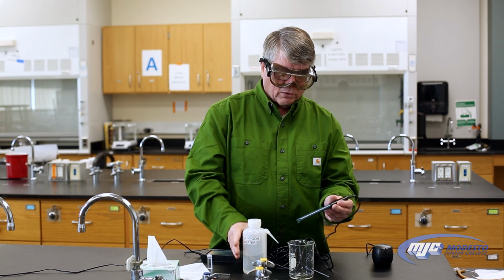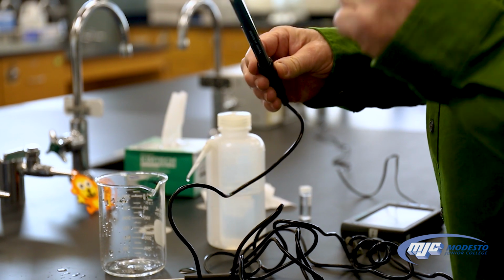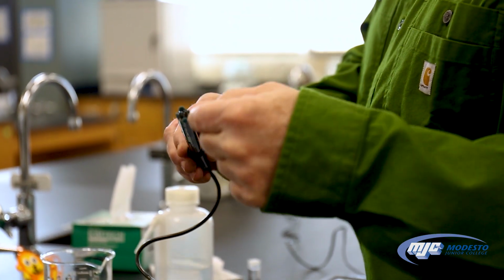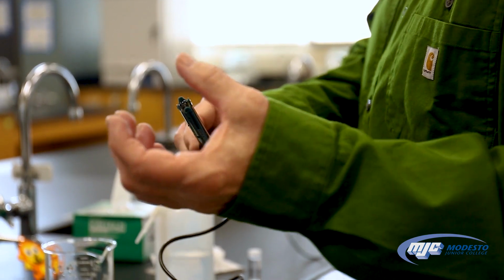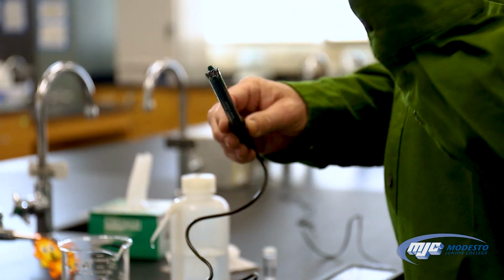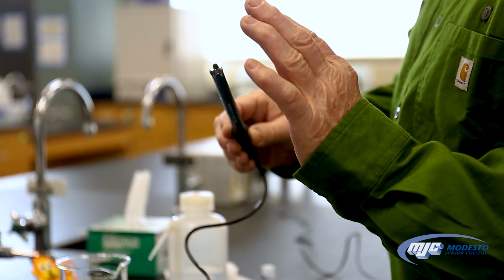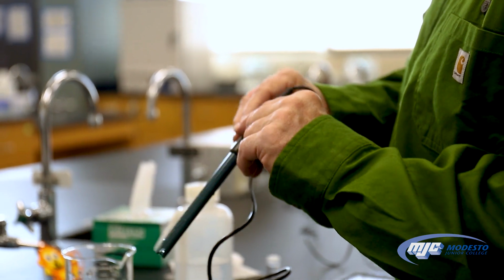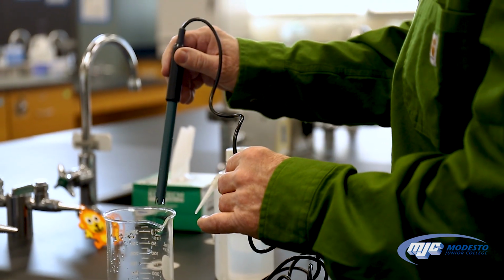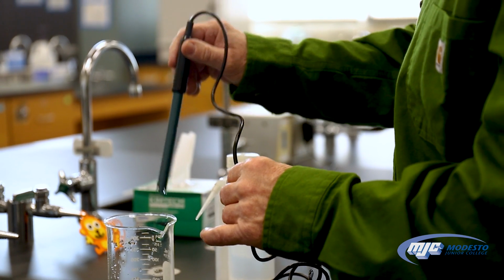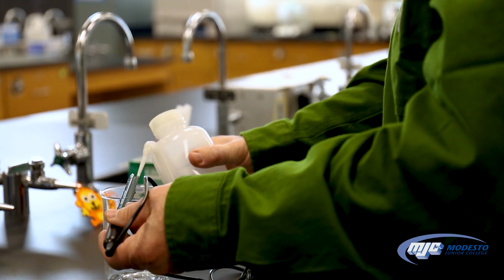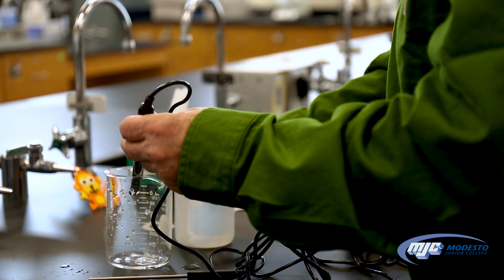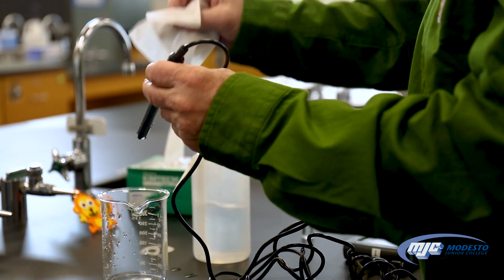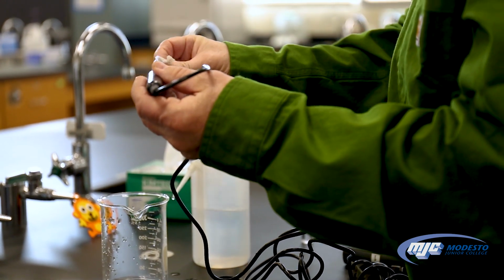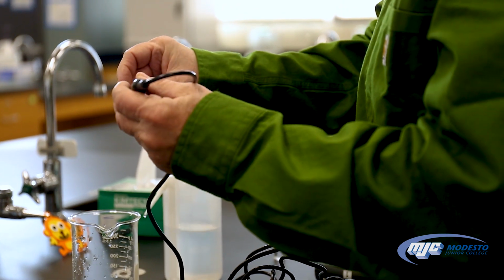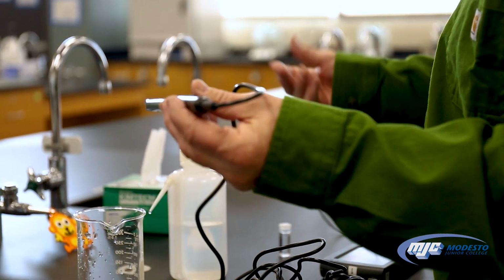Also, the functional part of this probe is this little glass tip right inside of the plastic protector. You want to clean that off too. You also want to be very careful. Please don't break that. If you break it, then the probe's ruined. Commonly what happens is people are not looking and they set it into a beaker to measure the pH and they don't quite get it in, and hit the edge and it breaks. So just be careful of that. So we want to rinse that off on the outsides with deionized water. Take a Kimwipe and gently wipe down the outsides and gently pat dry as much as you can that little glass bulb. So now we're ready to measure the pH of whatever solution.